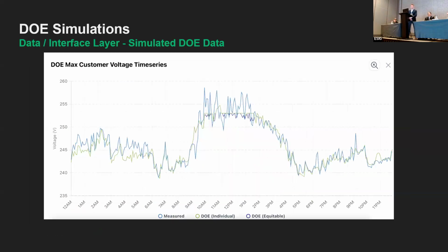This is showing the worst case voltage. So the customer that had the worst voltage excursions, in blue, on that particular substation, and the result of that curtailment. You can see the tan line, which is the predicted voltage that we optimize against, holds flat under that period. So it's really showing the effect, from a voltage perspective, of performing that curtailment.